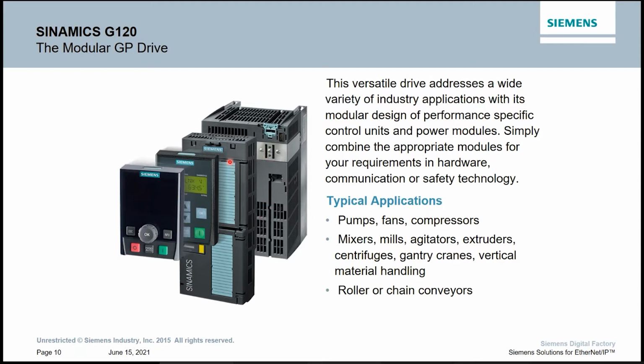What's nice about this is the actual control unit. So all the parameters, setup, and wiring is all on this control unit. So in a maintenance situation, if the power module, which is probably the most susceptible component for damage, gets struck by lightning, you click this off, change this out, and click that back on. From a spare part standpoint, you can stock one part for many different applications and have different control units.